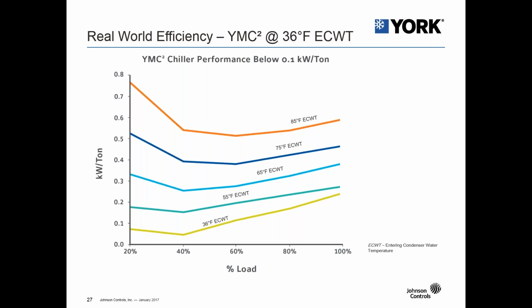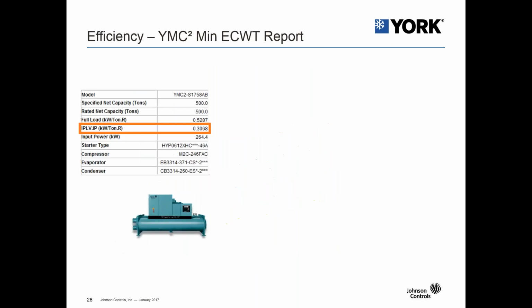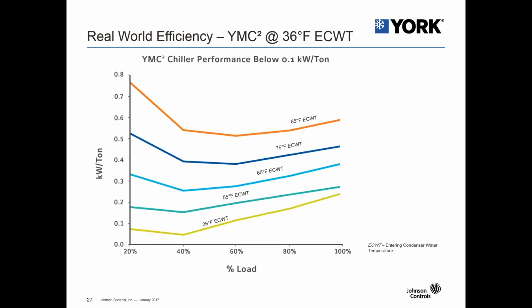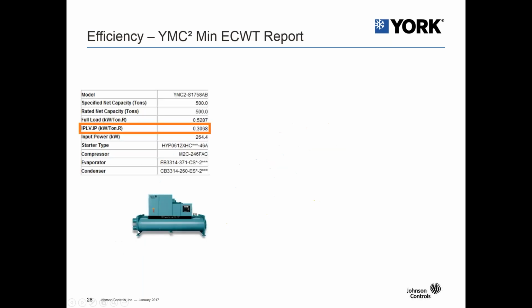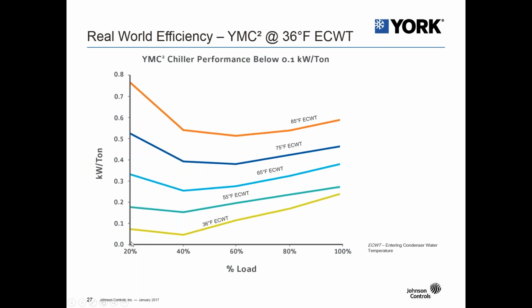So now when we jump back to the kW per ton curves that we were showing earlier, at 85, going from 100% load to 60% load with 85 entering condenser water temperature, we were only able to get 15% improvement on kW per ton. But if we're able to go all the way down to 36 degrees entering condenser water temperature, you can see down in the lower left-hand corner, we're able to get below 0.1 kW per ton.